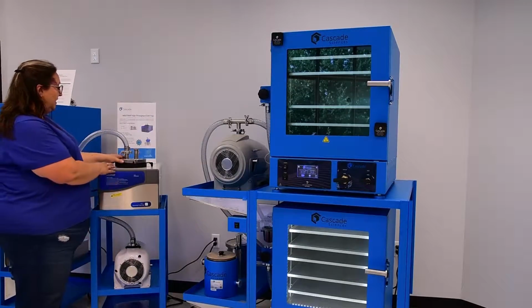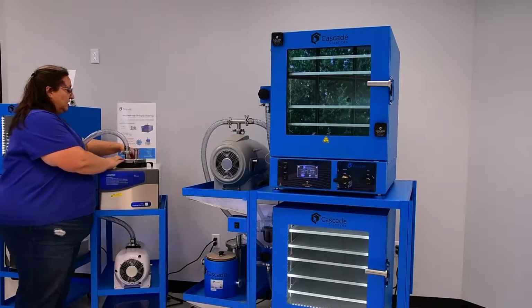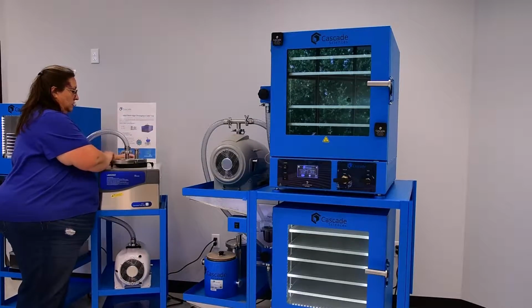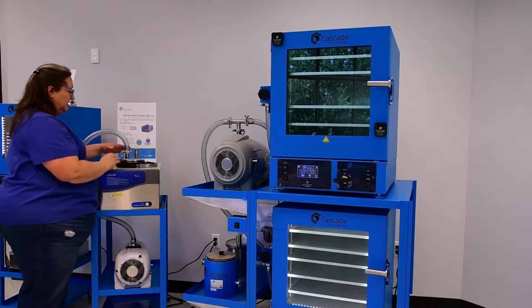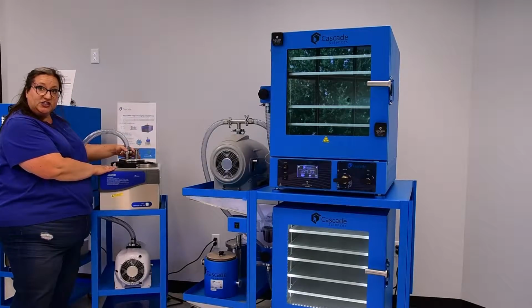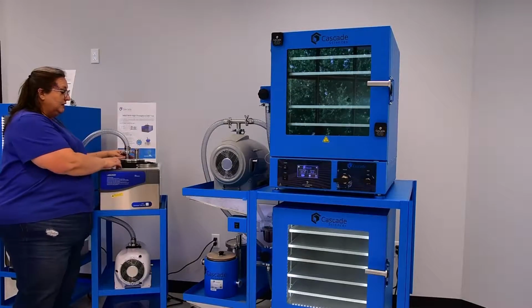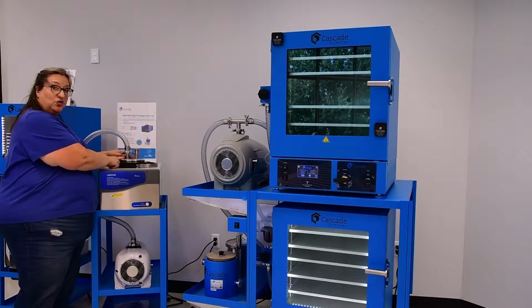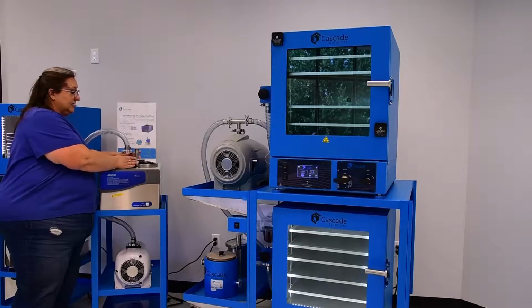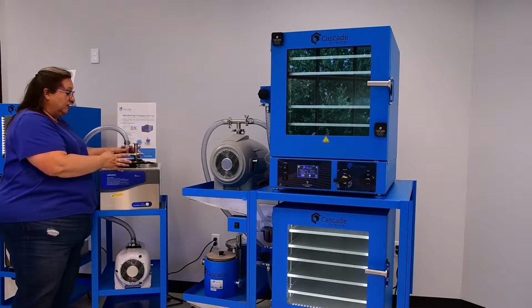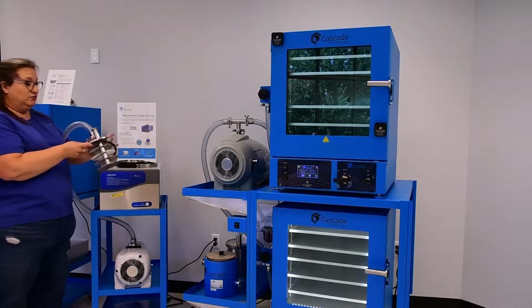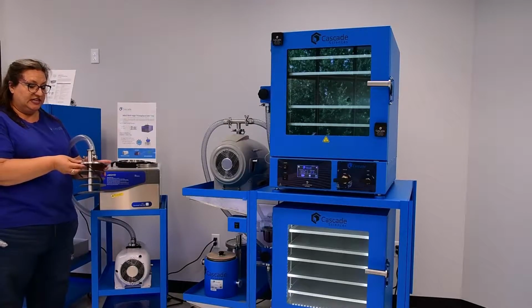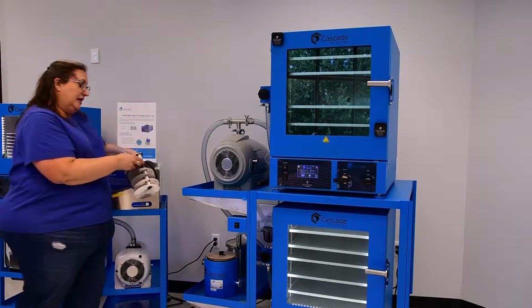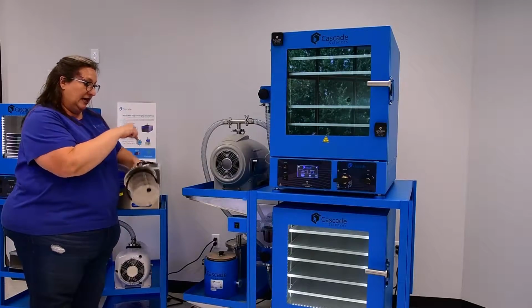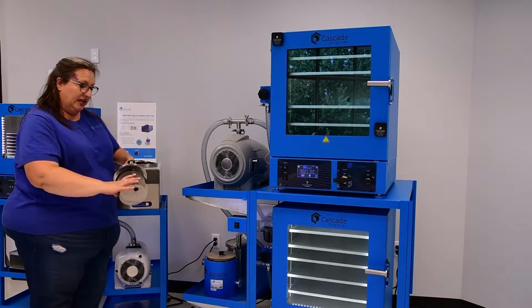So this refrigerated cold trap features our custom insert. So the standard cold well insert for one of these cold traps is glass. It has a plastic lid with a 1/4 inch intake and a 1/4 inch outtake. And those intake and outtake are right next to each other. So the gas path, which as we know from physics just takes the path of least resistance, that gas path just goes right in one side and out the other without ever getting cold.